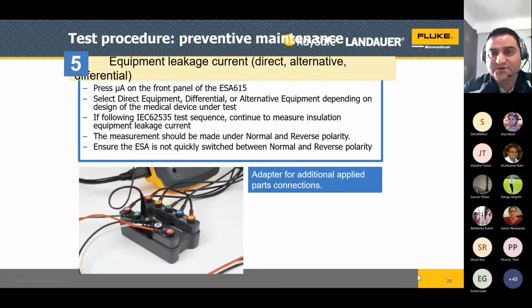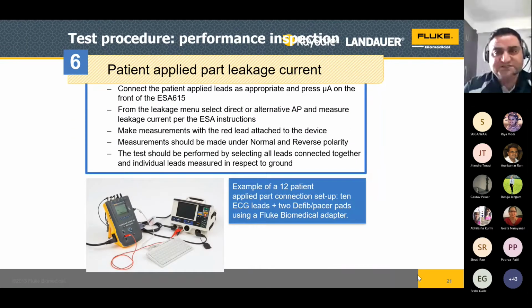Maybe there are some different permissible limits, which I will show you in one format. What are the permissible limits for single fault condition and normal condition? So those have to be followed actually. Patient applied part leakage currents. This means that suppose if you have an ECG machine, ECG leads are there. You can check one by one what are the leakages on each lead. Like if you have 10 leads, you can measure one by one on each for all the leads. It will tell you what the leakages are, whether it is within the permissible limits or not.